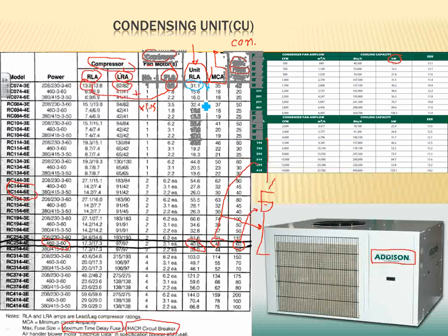You go to the NEC Article 430.250, the horsepower table, and say you came up with 100 amps, equivalent to, say, 100 horsepower. It's going to be 100 horsepower based on the full load amps. Then you also have to size it based on the locked rotor current.